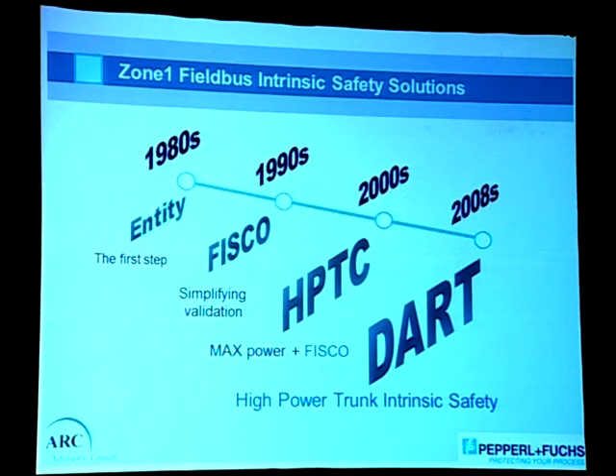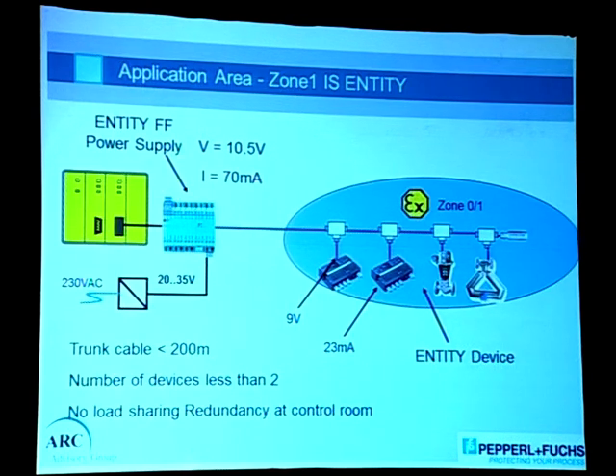Then we moved into a different type of intrinsic safety, what we call the high power trunk. This is one of the most adopted methods at the moment for intrinsic safety. And of course, it overcomes all the limitations, whether by the entity or FISCO way of doing Fieldbus intrinsic safe or hazardous area application. Though it meets almost every requirement, it still has some limitations. The trunk and the spur have to follow different standards. The spur lines, from the field junction box to the device, can be intrinsically safe, but from the control room all the way to the field junction box, we still need to bring higher energy, so that cannot be intrinsically safe.